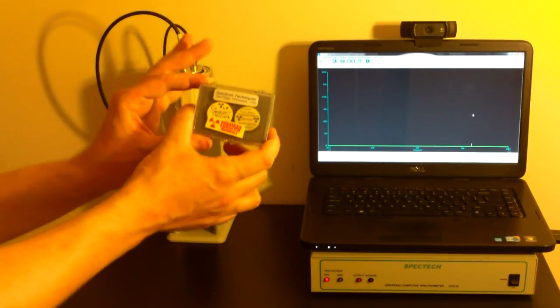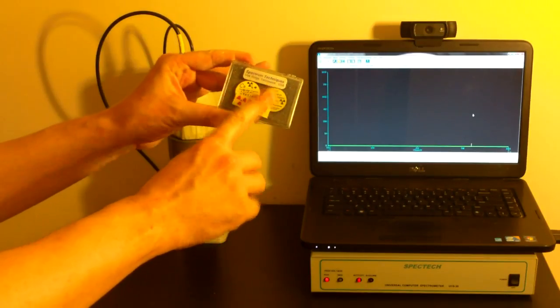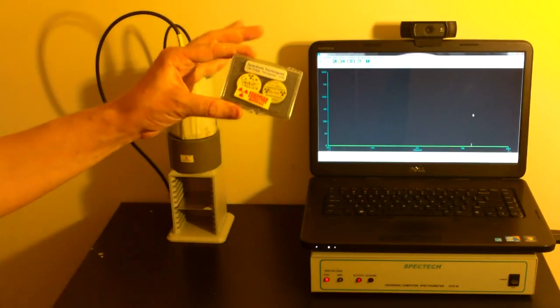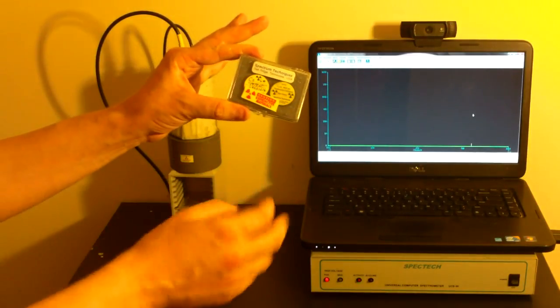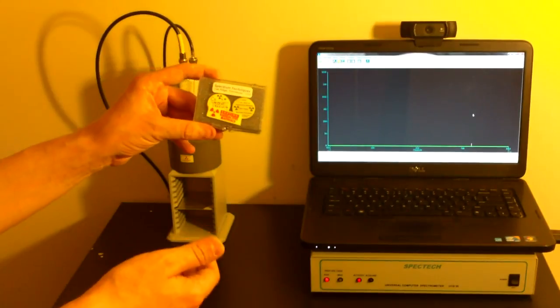We are going to determine the characteristics of cobalt-60, which is this little guy right here. These are two check sources I have. This one is cesium-137 for calibration. This one is cobalt-60, which is what we're going to be looking at.